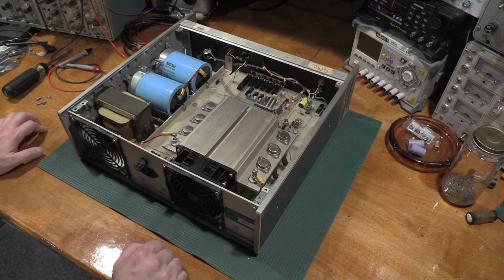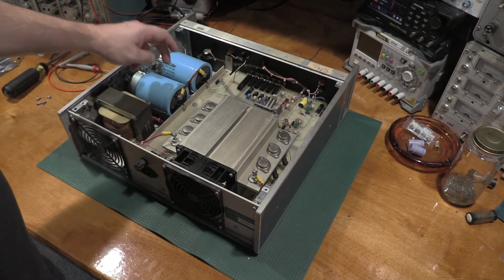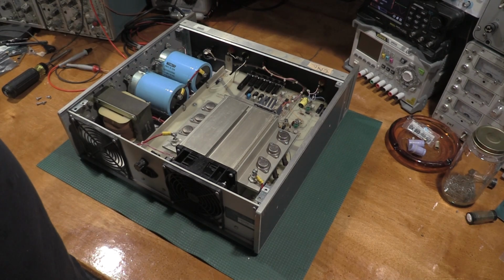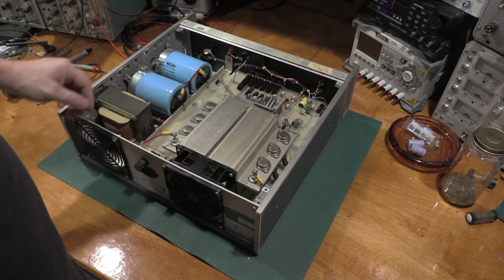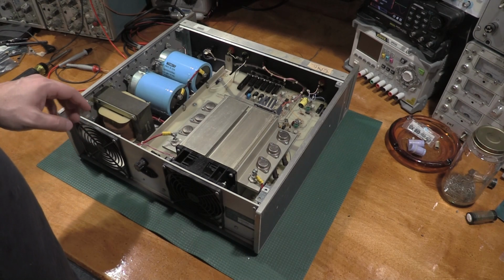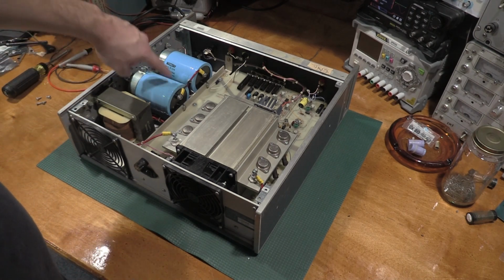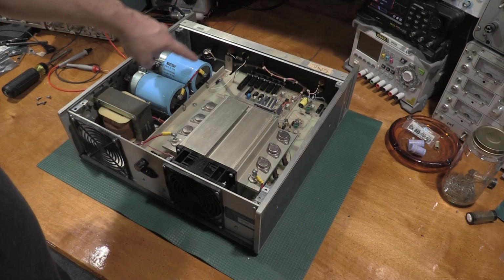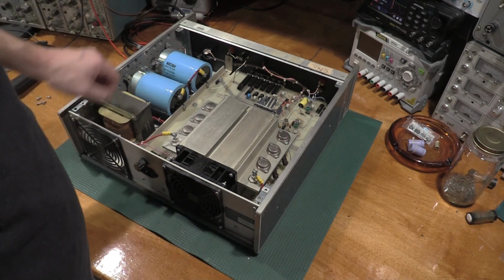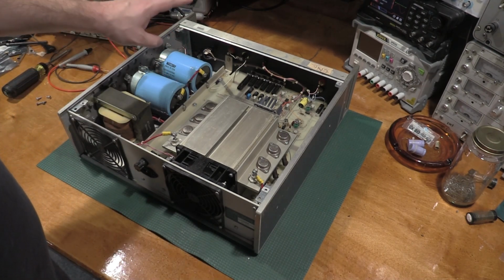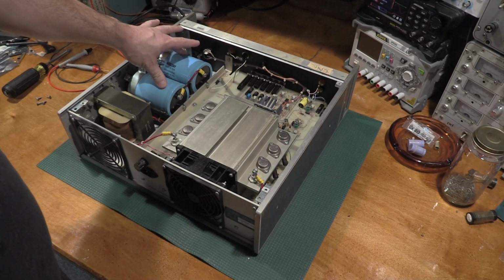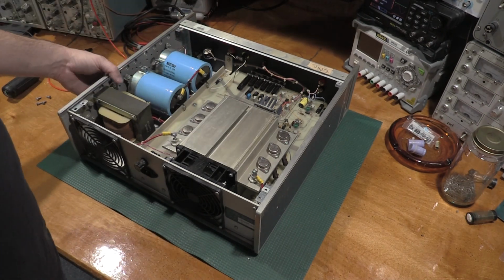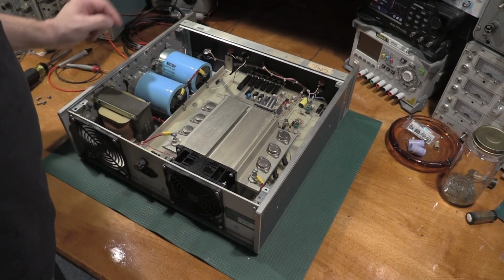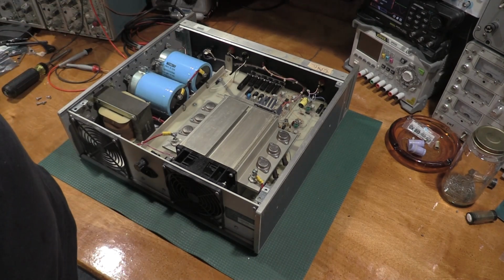55,000 microfarads at 40 volts working volts DC. So not a ton of voltage, but there's current behind there. Holy cow. And we do see one's wired up with the black and one's wired up with the red. So this is probably going to be our positive and negative supplies going into there, I would suspect. But nice big beefy parts there.